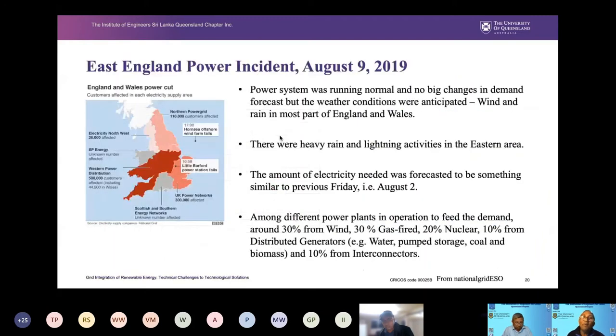And something similar happened in the East England incident. The main point I would like to highlight from the previous incident is that we had significant generation from wind farms. And then perhaps if we had synchronous generators, we could have avoided it, but that doesn't mean that the wind farms are bad. We should have just put some control measures in place, at least as a last line of defense. We should have put in some load shedding to protect and safeguard part of the system.